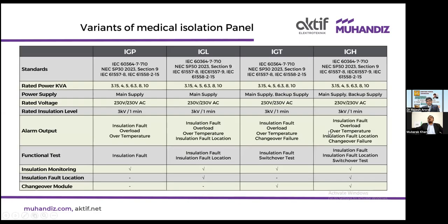Now the medical isolation panels with all these products and features come in various types. The first one is the basic one, which is required as per NEC standard: a device with isolation transformer and insulation monitoring device, which will detect only the insulation fault. The second one is insulation fault with insulation fault location system. Third is insulation fault with automatic changeover from main power to UPS power. And the more advanced one is insulation fault with insulation fault location and automatic changeover system. So these are the various varieties, and we can select as per our design and budget.